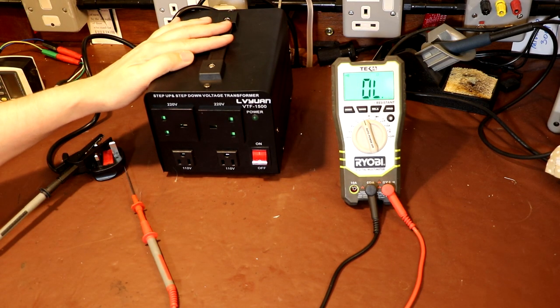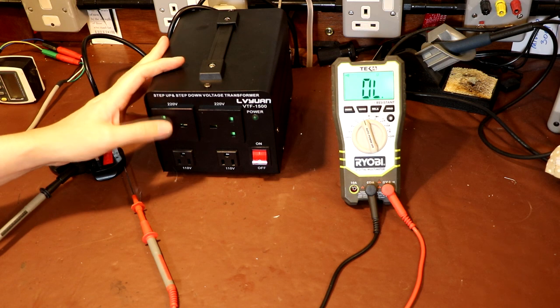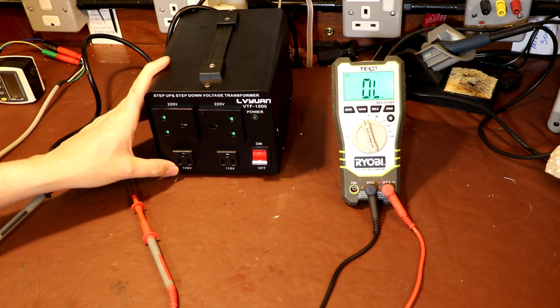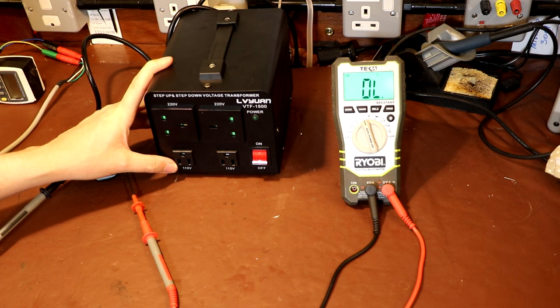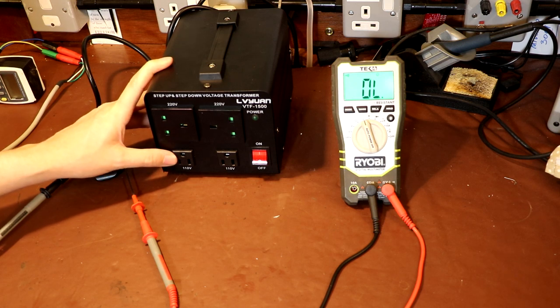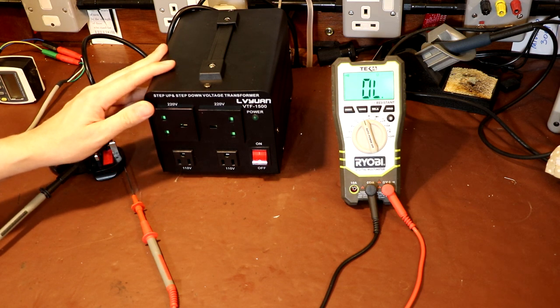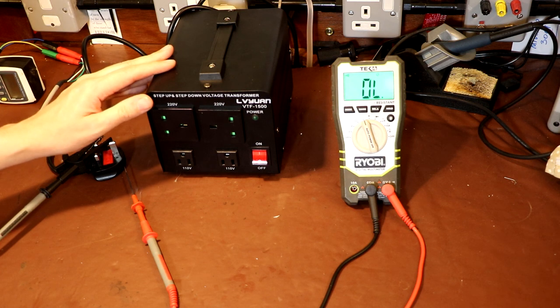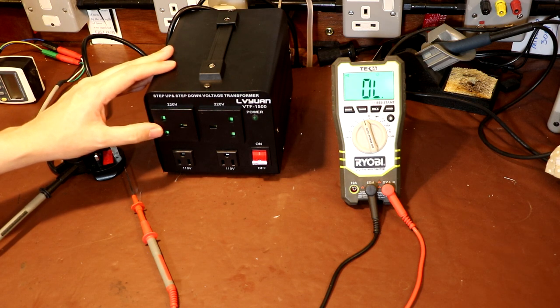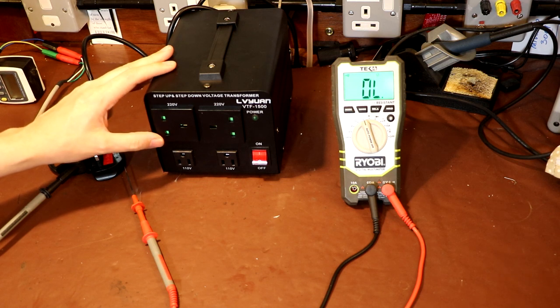So in this application there is absolutely nothing wrong with using an auto transformer. It's probably the perfect application for it. It really isn't a big deal if we have a fault, and the worst that can happen is we can get 220 volts put on our 110 volt output. It may damage the piece of equipment that's connected to it, or it may just blow a fuse, but it's unlikely to result in an injury to anybody. So for this type of application, the fact that they can make the transformer much smaller, much more cheaply, and it also has advantages in terms of efficiency and voltage regulation, it's an all-round winner. But there are very many applications where an auto transformer would be absolutely the worst thing to use.